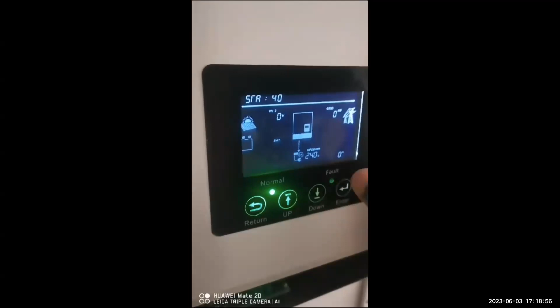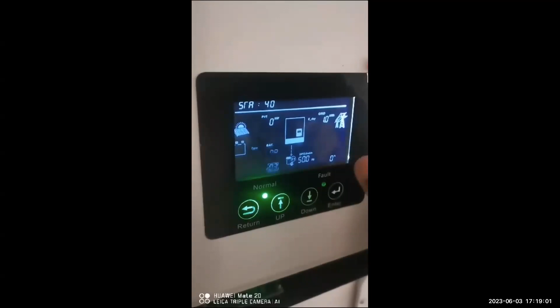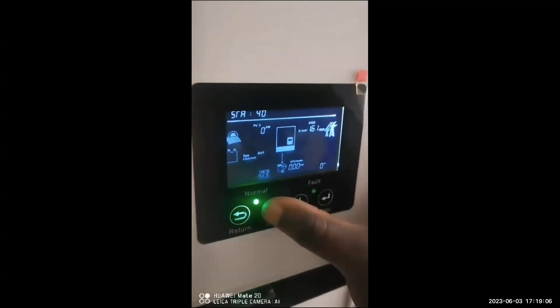In this case, we're going to program it as a lithium battery. So David's going to go back down to lithium shortly, you'll see him do that now. Lithium, then he's going to press enter, and then you'll select your battery protocol brand. A lot of people know number 2 to be Pylon-Tech. Once that's selected, the inverter will restart. Since this is already programmed on a battery, we're not going to hit enter, so we'll just return. Okay.